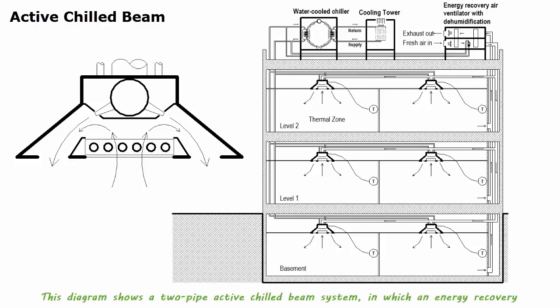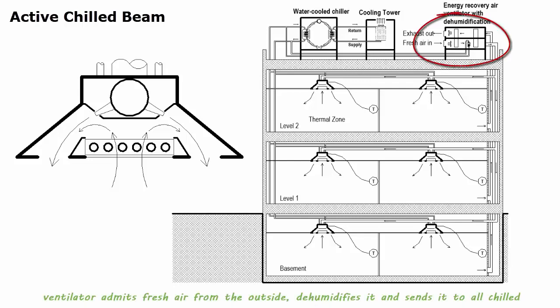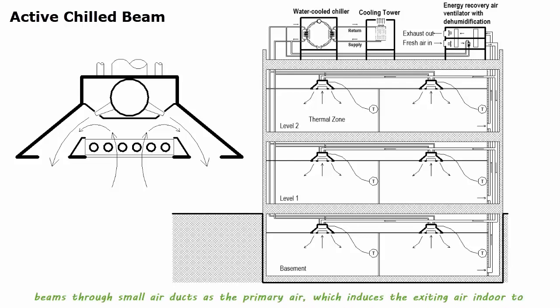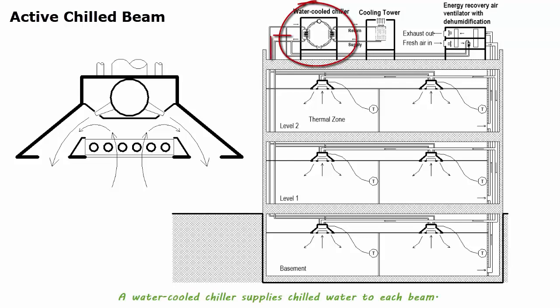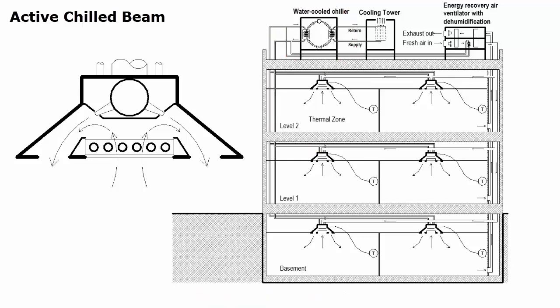Therefore, the primary air must be dehumidified to the level that will not cause condensation in the units. This diagram shows a two-pipe active chill beam system in which an energy recovery ventilator admits fresh air from the outside, dehumidifies it, and sends it to all chill beams through small air ducts as the primary air, which induces the existing indoor air to pass through the chilled water tubes within the chill beams. A water-cooled chiller supplies chilled water to each beam.